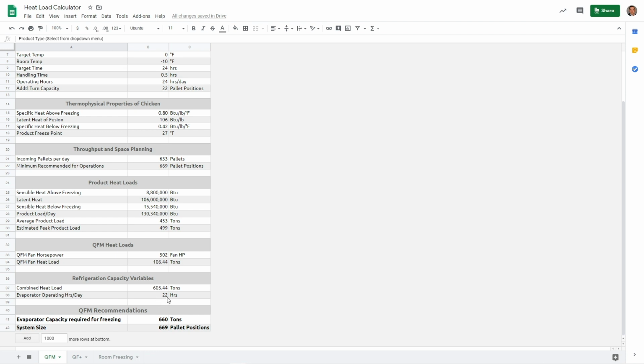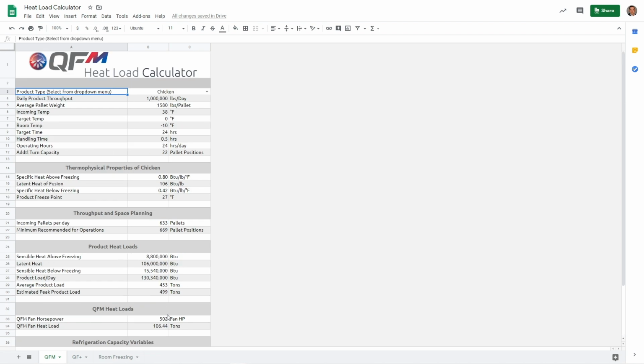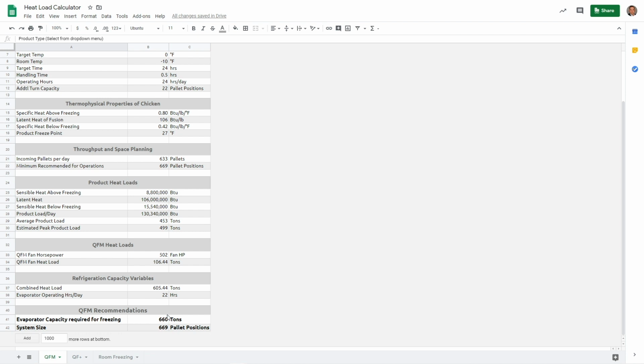Then we look at the net operating hours for the evaporators in the space. In this example, we ran with 22 hours. That gives you 2 hours worth of defrost per day. So this example is netting us a suggested evaporator capacity of 660 tons, and then 669 pallet positions. Now, obviously, this 660 tons, you'd have to add in other loads: envelope loads, other lighting and material handling, ingress. All of that really needs to be added to that figure. But what we're trying to do is quantify the heat load that we're kind of responsible for in the room.